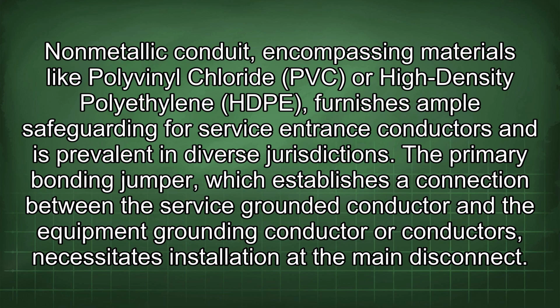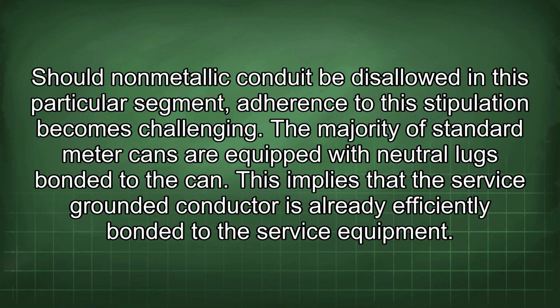The primary bonding jumper, which establishes a connection between the service grounded conductor and the equipment grounding conductor or conductors, necessitates installation at the main disconnect. Should nonmetallic conduit be disallowed in this particular segment, adherence to this stipulation becomes challenging.